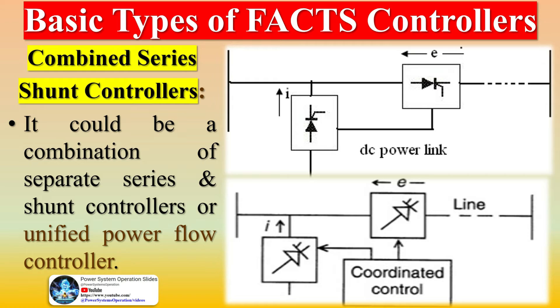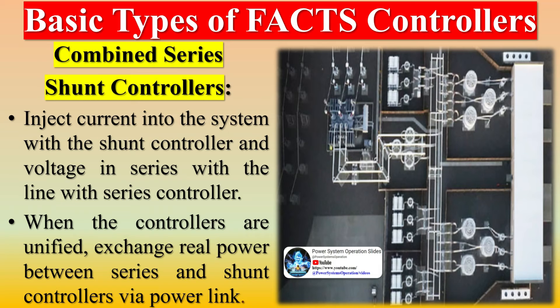Combined series-shunt controllers could be a combination of separate series and shunt controllers or a unified power flow controller. They inject current into the system with the shunt controller and voltage in series with the line with the series controller. When the controllers are unified, real power is exchanged between series and shunt controllers via a power link.